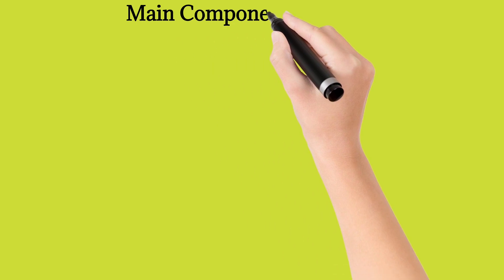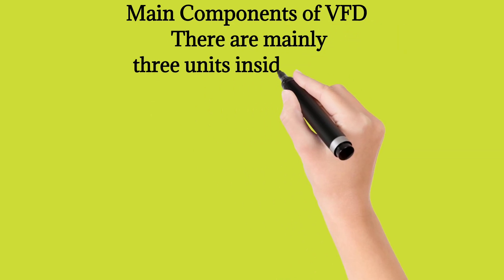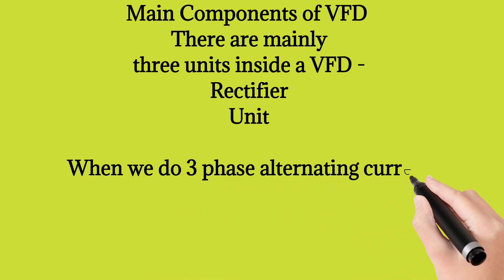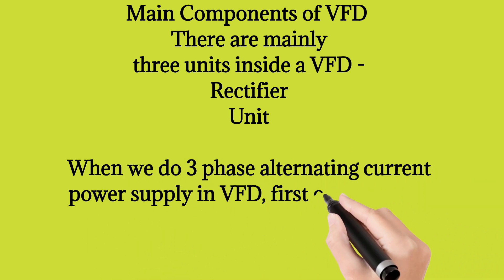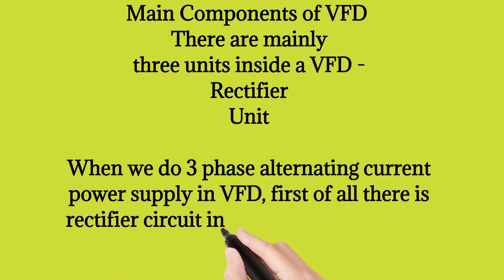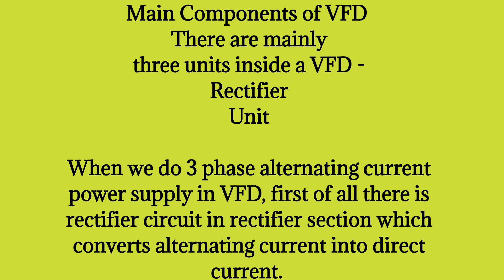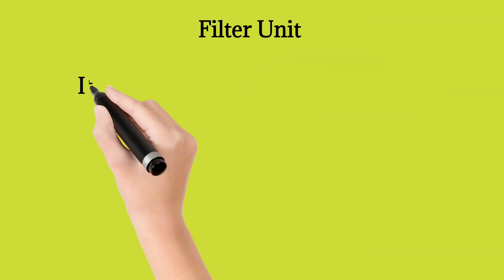Main components of VFD: there are mainly three units inside a VFD. First, the rectifier unit. When we supply three-phase alternating current power to VFD, first of all there is a rectifier circuit in the rectifier section which converts alternating current into direct current. The filter unit has a capacitor which eliminates the ripples produced by the direct current, because when AC is converted into DC in the rectifier section, it does not completely convert, hence some ripples are generated.